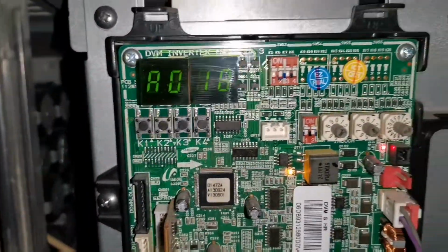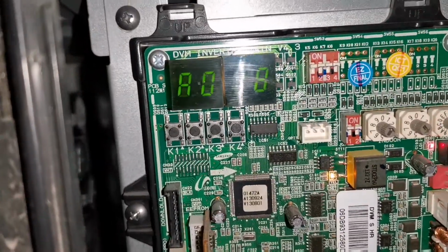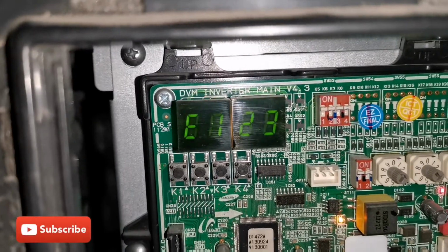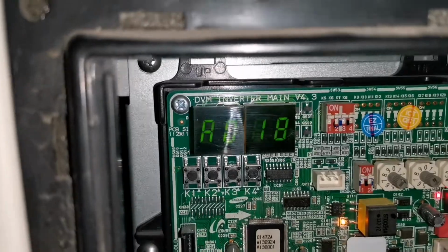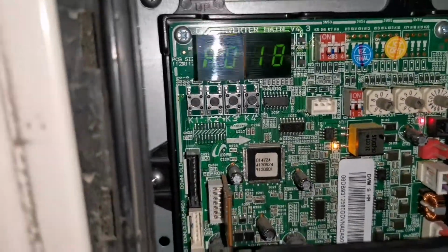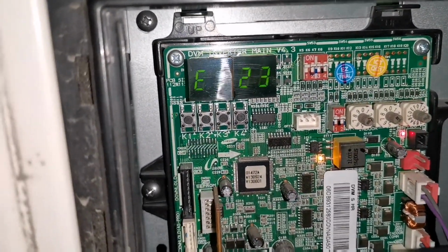What's up, guys? So we've got an E123 error code, and if you have a look, the second display says E123, then it goes to A018. So it's actually telling us on which Indoor unit we've got that error code, and that's address number 18 or 018.